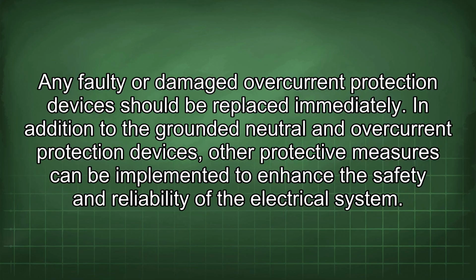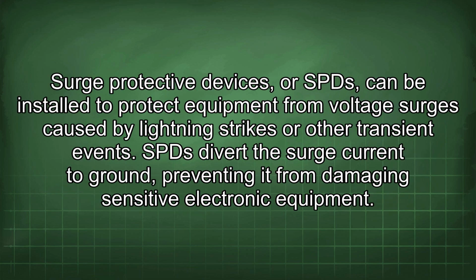In addition to the grounded neutral and overcurrent protection devices, other protective measures can be implemented to enhance the safety and reliability of the electrical system. Surge protective devices, or SPDs, can be installed to protect equipment from voltage surges caused by lightning strikes or other transient events. SPDs divert the surge current to ground, preventing it from damaging sensitive electronic equipment.